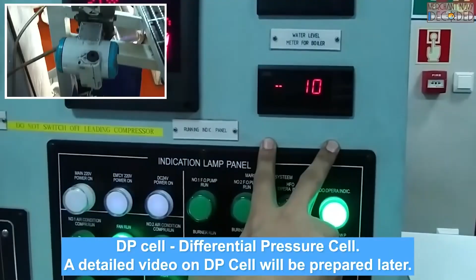Accordingly, there is a steam pressure transmitter fitted on the steam side, which tells us the steam pressure. Now, understand one thing. This is all automation. On a ship, we should not rely completely on automation, because one small mistake and we are screwed. So apart from the water level alarm coming in the ECR, there is a separate individual system on board, a float system, completely independent of automation. If that float comes down, it gives a low water trip, and the boiler trips straight away.